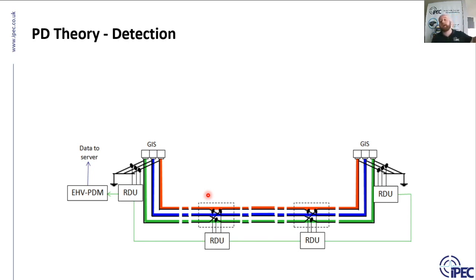Equally, installing sensors along a cable means you get increased sensitivity. As you would imagine, the smaller PDs are detected more easily, so it is better in EHV applications to install sensors along the actual circuit itself. And the nice thing with EHV, of course, is the earth is separated from the core at these points along the installation. Just another note, they're not necessarily the nicest environments. However, we do have solutions for monitoring in these environments. We can monitor with IP-rated enclosures, we can use fiber optic for communication, and we can install underground.